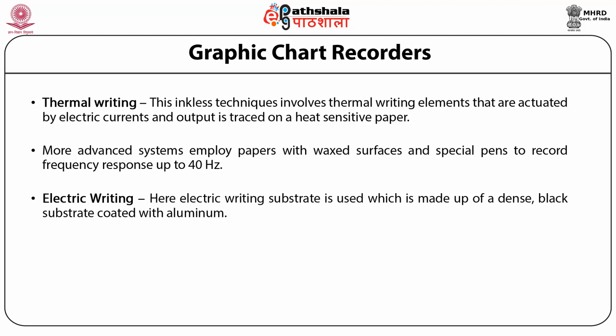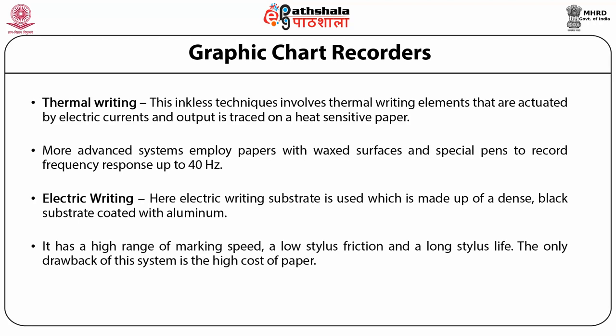D. Electric writing: A substrate made of a dense black material coated with aluminum is used. A tungsten wire stylus is kept in light contact with the aluminum surface. When voltage is applied, aluminum is etched and the black substrate is exposed. A minimum of 35 V DC is applied at a frequency of 8 Hz to avoid possible grounding via the aluminum chart. It has a high range of marking speed, low stylus friction, and long stylus life. The only drawback is the high cost of paper.